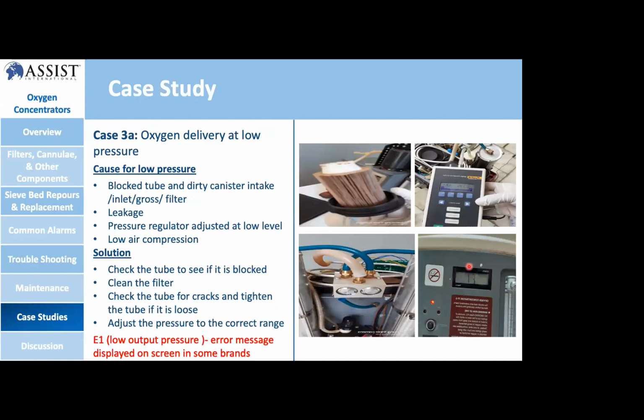In case three, we have two cases. Case 3A is oxygen delivery at low pressure to the patients. This is caused by a blockage of the tube or a dirty canister intake filter or gross filter. That means in a canister below the O-ring, we have a filter. If it is blocked, it lowers the pressure output from the canister or sieve, so it causes low pressure at the output.